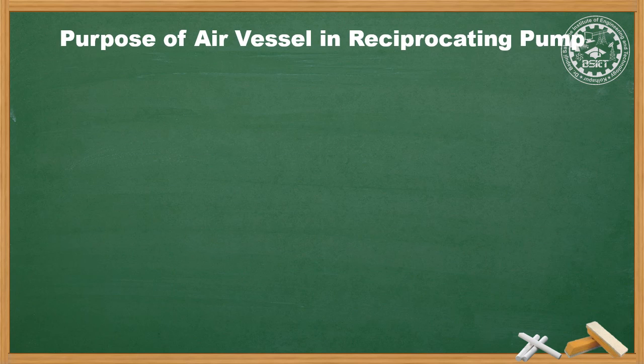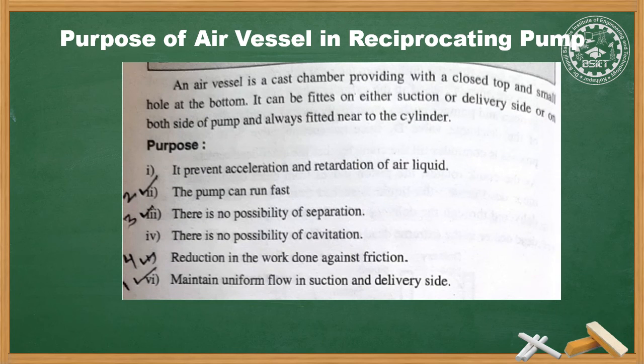The purpose of the air vessel in a reciprocating pump: an air vessel is a closed chamber with a small hole at the bottom, fitted on either the suction side, delivery side, or both, always near the cylinder. Its purposes are to prevent acceleration and retardation of the liquid, allow the pump to run faster, eliminate the possibility of separation and cavitation, reduce work done against friction, and maintain uniform flow in suction and delivery pipes.